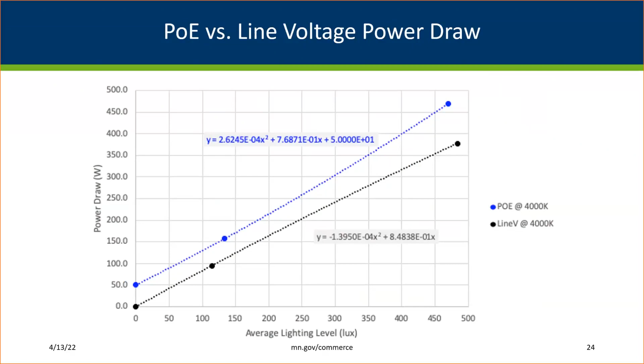From the result chart, we can see that the two lines have pretty similar slopes, but the PoE system has a non-zero standby usage. This is associated with the use of the network switch. So comparing the PoE system to an AC-powered digital addressable lighting interface lighting system, which is also called a DALI lighting system, or a digital multiplex, a DMX lighting system, might be a more apples-to-apples comparison in both functionality and the standby needs.